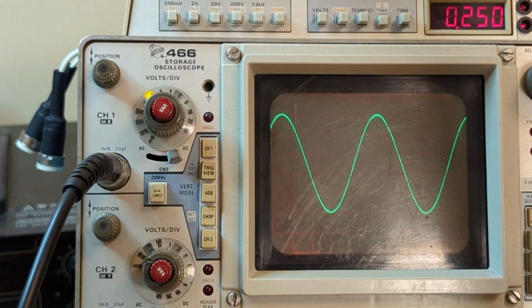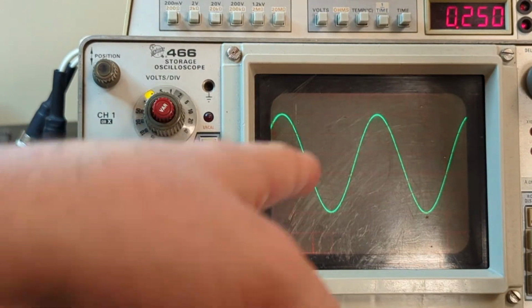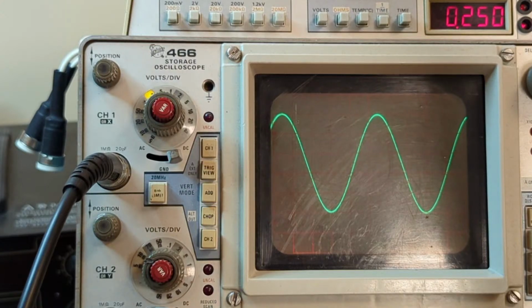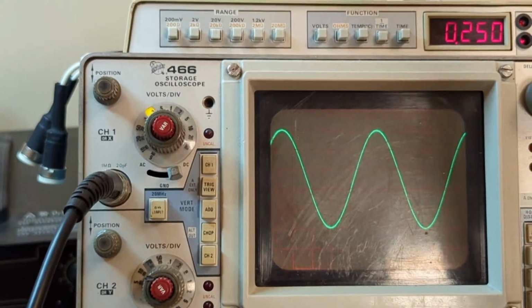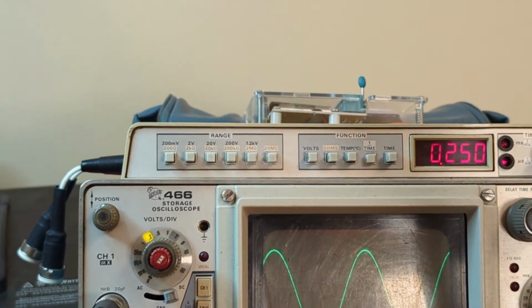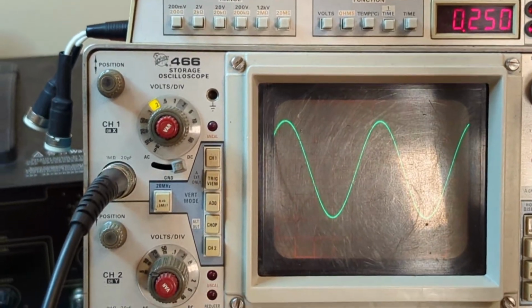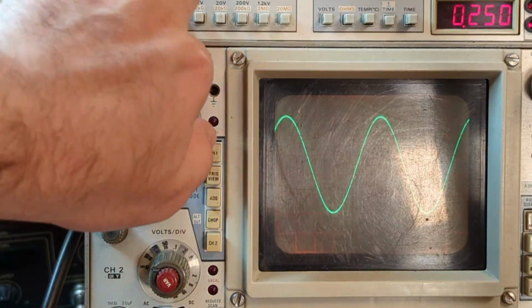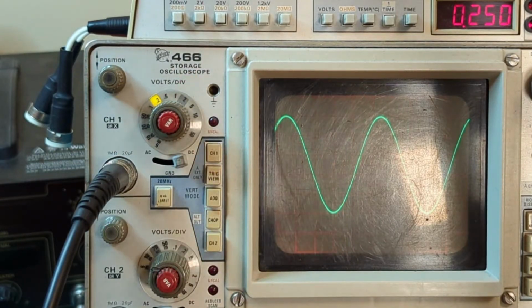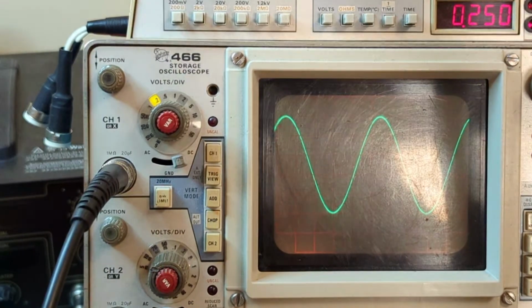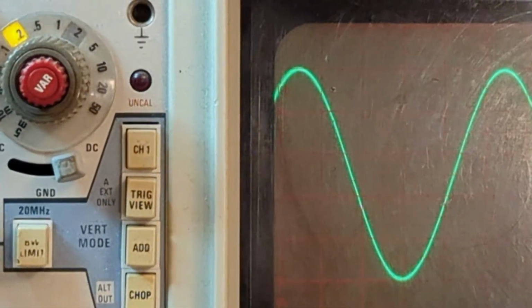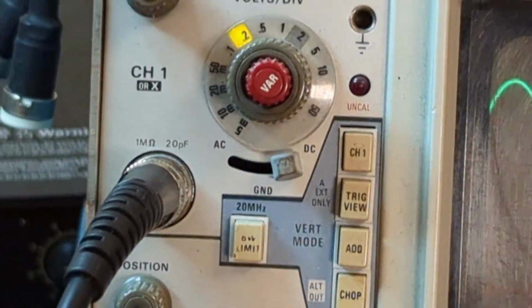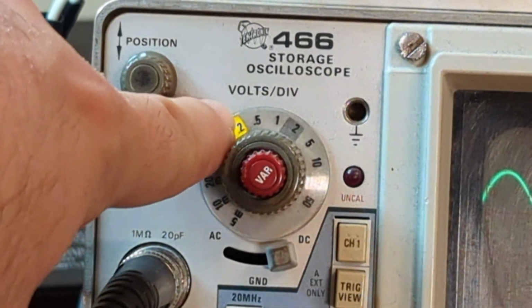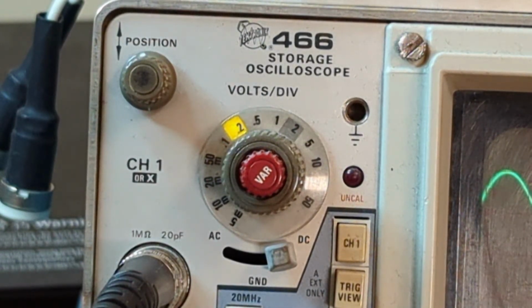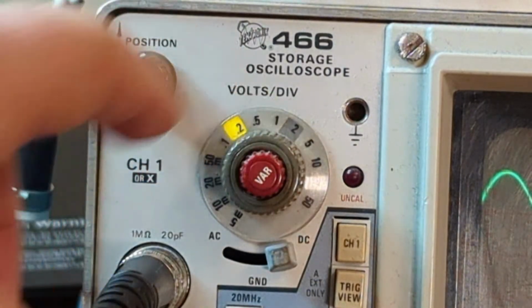However, the nice thing about this is that the scopes are calibrated, and you can actually use them to measure the amplitude. So let's see how we can do that. For this, it would be ideal for this phone to be slightly higher, because this will help us see the vertical sensitivity setting. For analog scopes, we usually have a rotary knob like this one, and the sensitivity is right here where the orange light is. Let me see if I can zoom in on that. Okay, so the vertical sensitivity is 0.2, as the Americans like to call it, meaning 0.2, and the unit is volts per division. Let's see what this means.